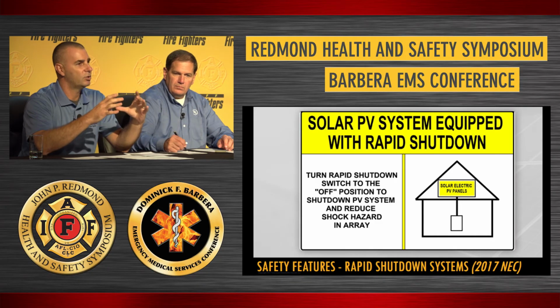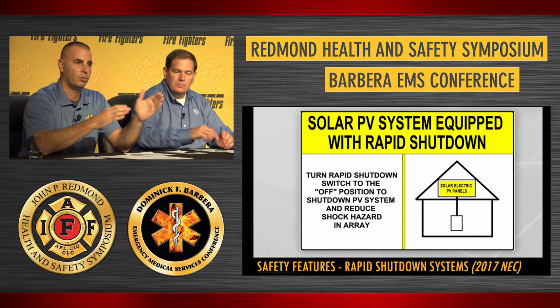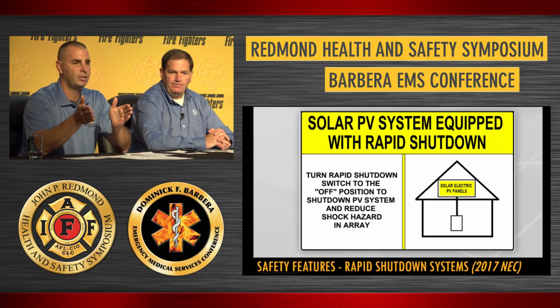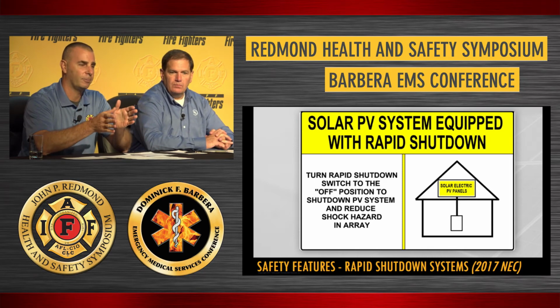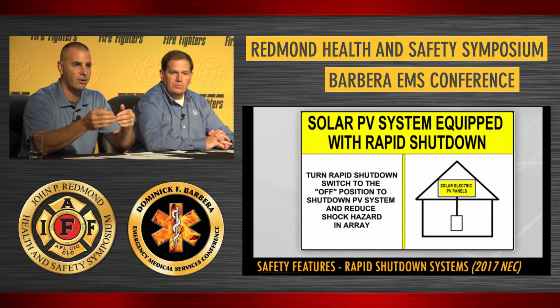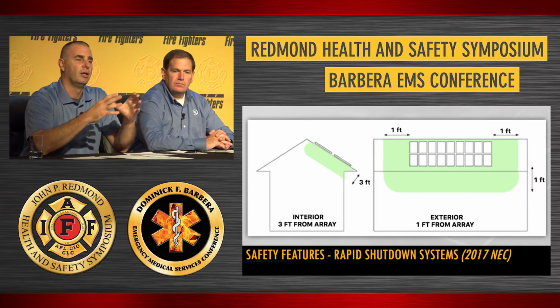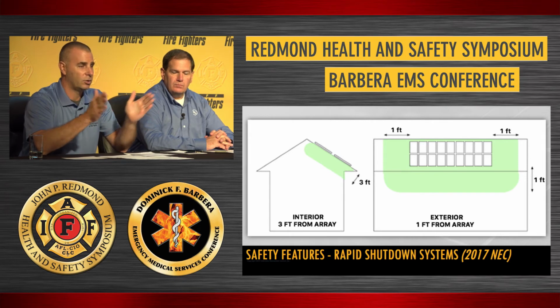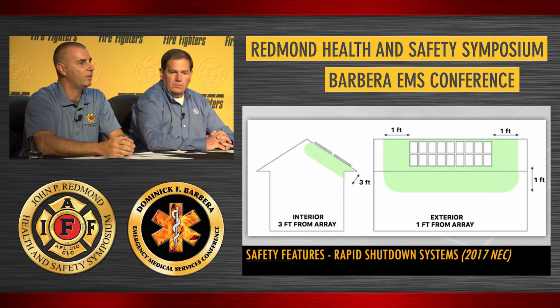The reason they came up with a new sticker is that there's a difference between the 14 code and the 17 code. You'll notice this is yellow, with a yellow and a white background. Where the differences come in is that the boundaries changed. So that 10-foot boundary that we had drops down to 1 foot. So it made it a little bit safer for us. The interior boundary dropped down to 3 feet.